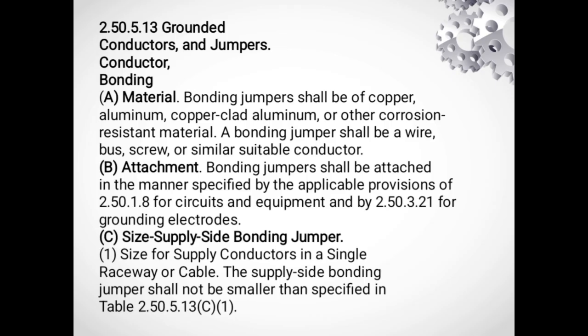2.50.5.13 Grounded conductors and jumper conductor bonding. A. Material. Bonding jumper shall be copper, aluminum, copper-clad aluminum, or other corrosion-resistant material. A bonding jumper shall be a wire, bus, screw, or similar suitable conductor. B. Attachment. Bonding jumpers shall be attached in the manner specified by the applicable provisions of 2.50.1.8 for circuits and equipment and by 2.50.3.21 for grounding electrodes.